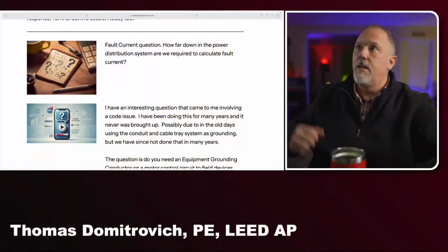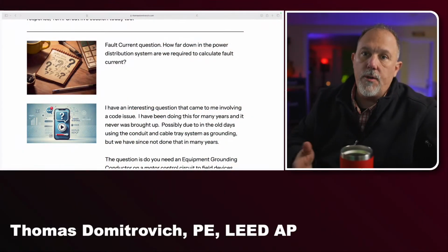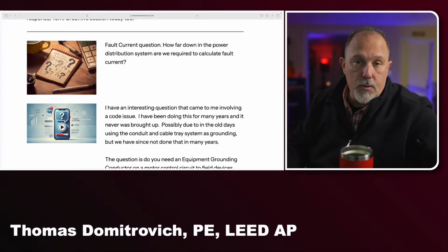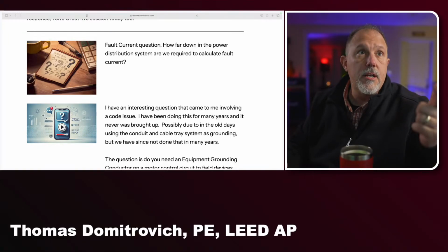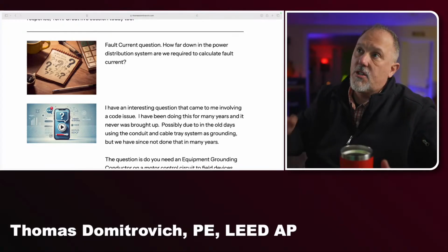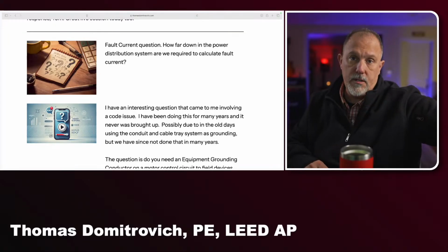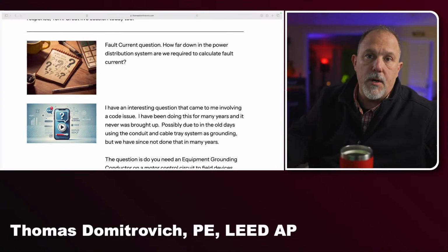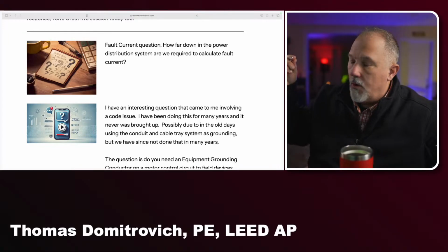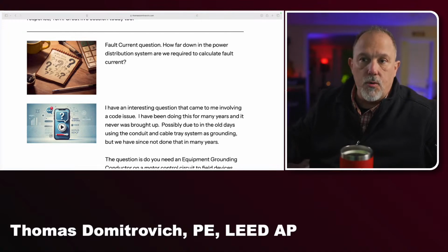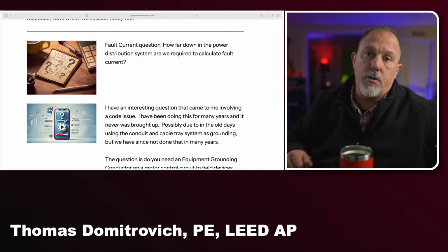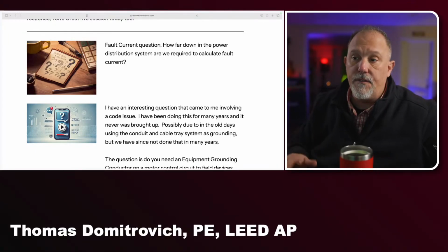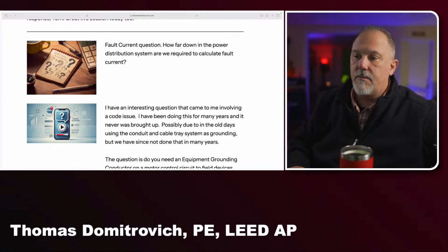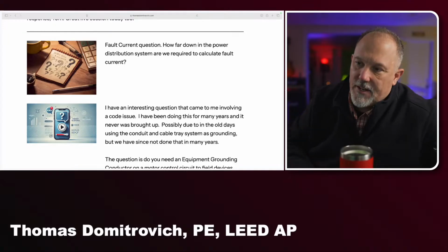All right. So my answer to this question, how far do we have to go? Well, we can look at the code, and we know the code has specific requirements for panel boards, switchboards, and switchgear. Also, industrial control panels, motor control centers. There are various areas in the code, but regardless of the code requirement, how far you need to go down depends upon the component you're trying to ensure has a correct interrupting rating or a short circuit current rating. That's going to dictate how far down you need to go in the system. Yeah, Steve, I caught the 10,000 amps. I figured everybody else did too.